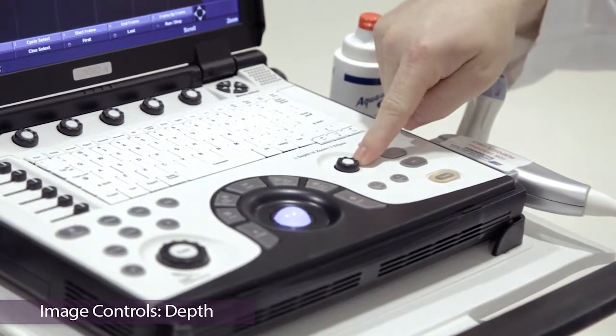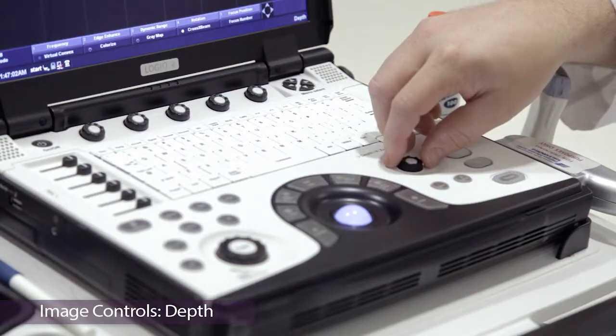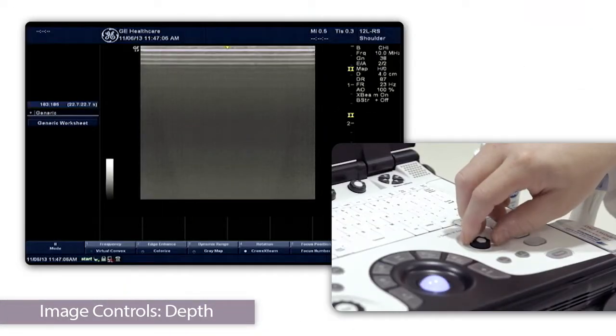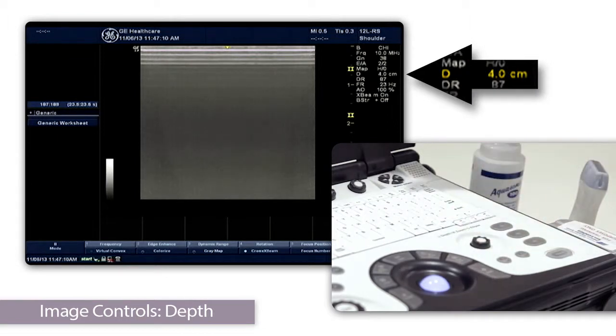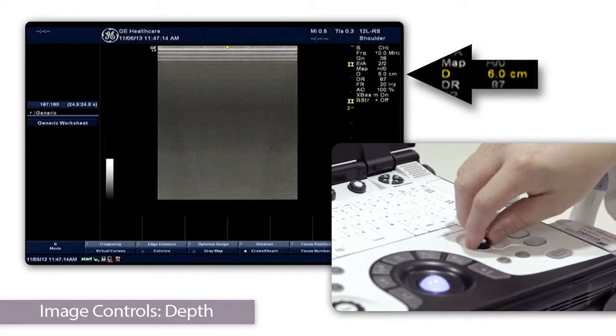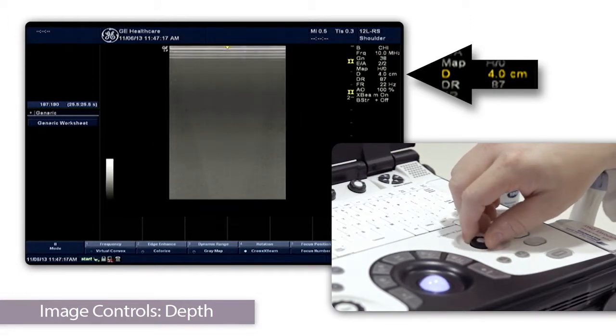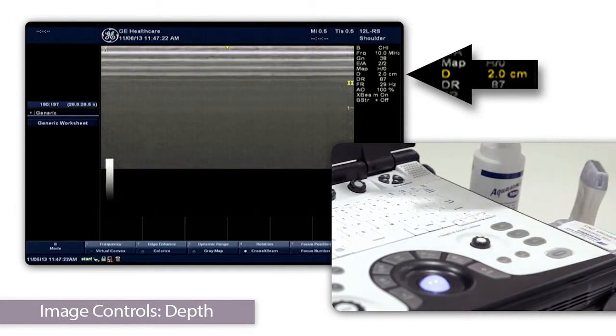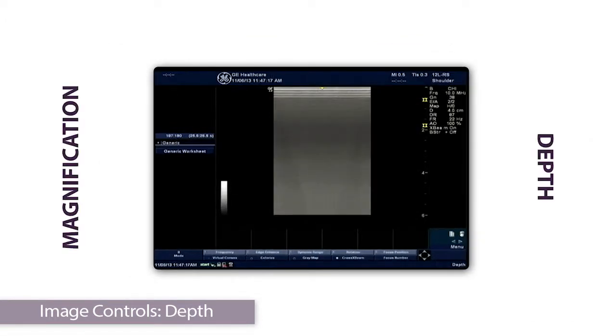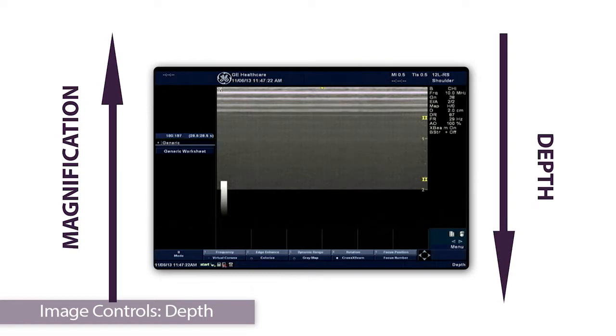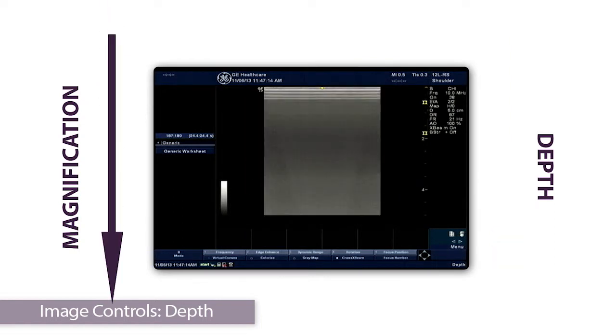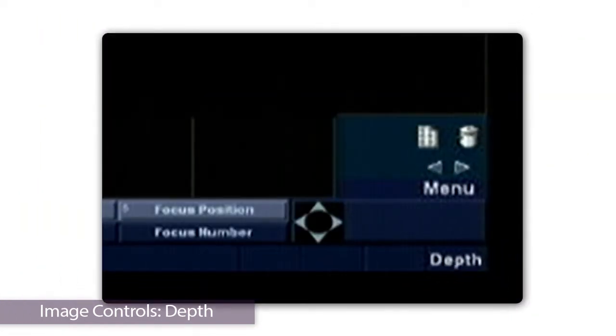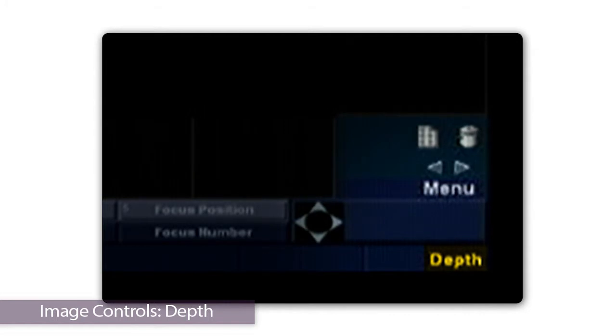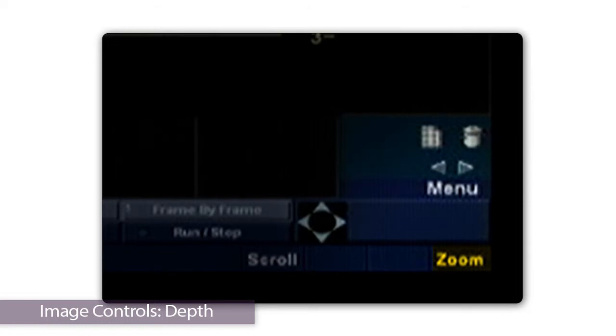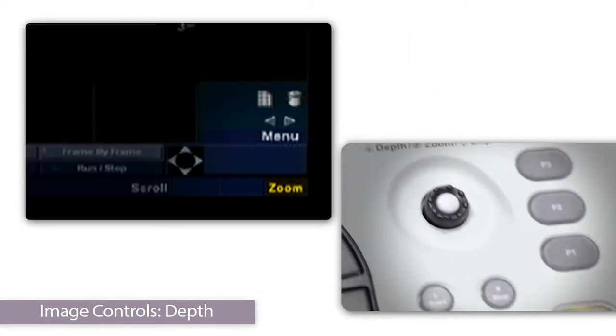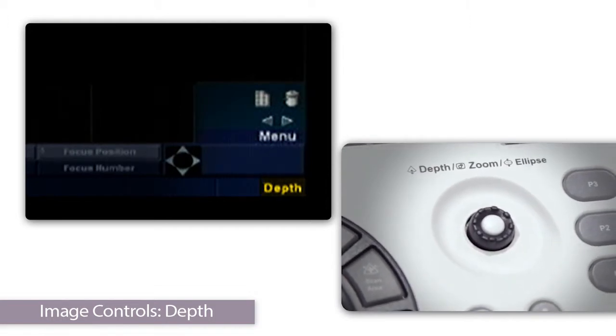Right here on the GE machine is the depth knob. And to change the depth, one just needs to twist this knob. As I twist it to the right, you can see that the depth increases slowly now to 4 centimeters. Twist it a little more, 5, 6 centimeters. If I twist to the left, I can reverse it. And as I twist, I can go as shallow as 2 centimeters. Note that the magnification of the screen increases as the depth is lowered, and it actually shrinks in magnification as the depth is greater. Please be sure that it says depth in the lower right corner of the machine. If it happens to say zoom, make sure that the screen is not frozen by clicking the freeze button to turn it off, and then you can push the button that's actually on the depth knob to remove it from zoom and make this say depth.